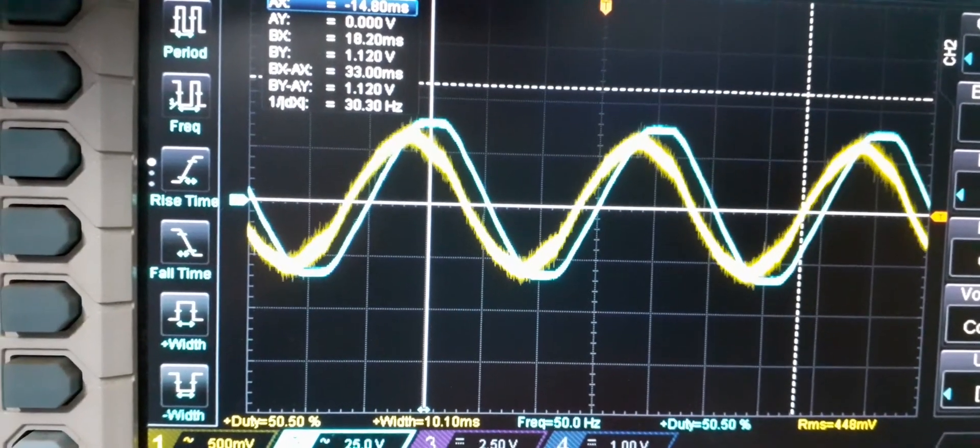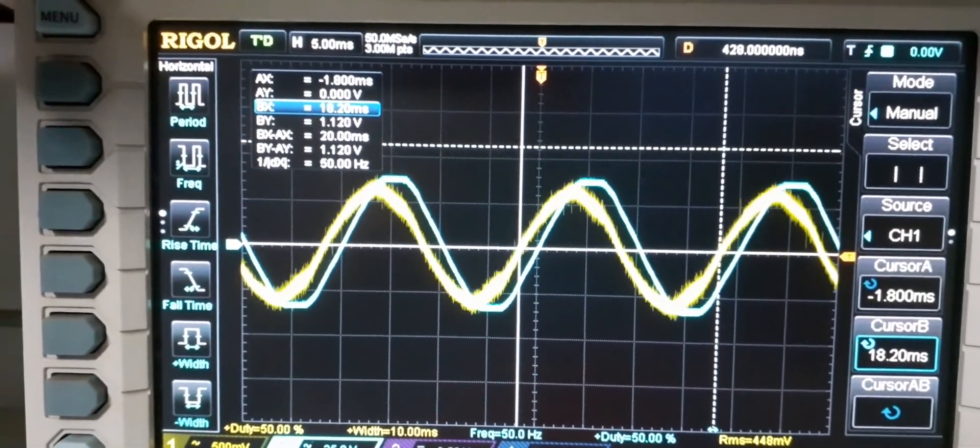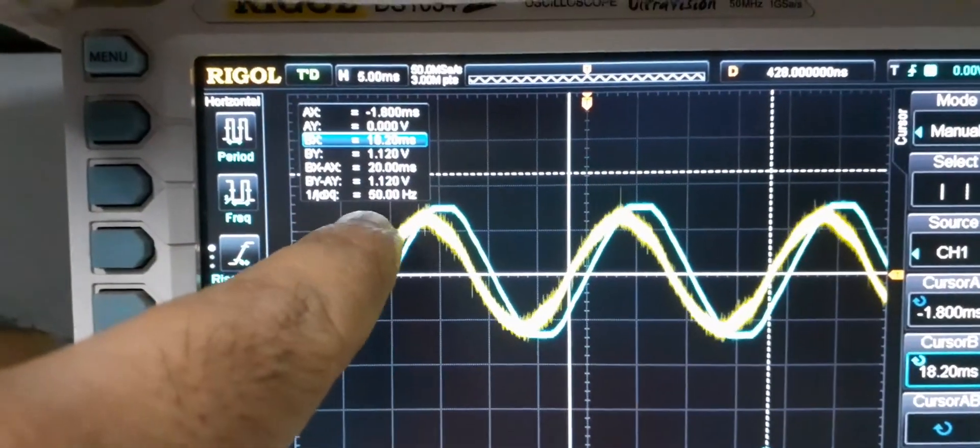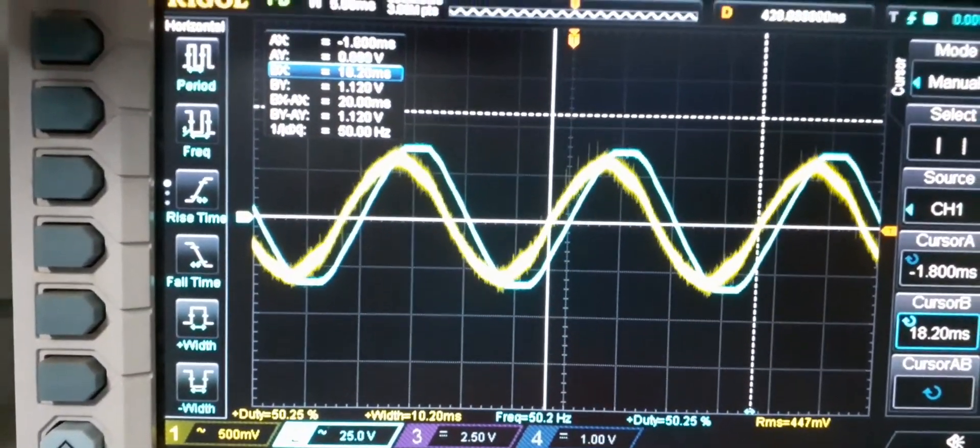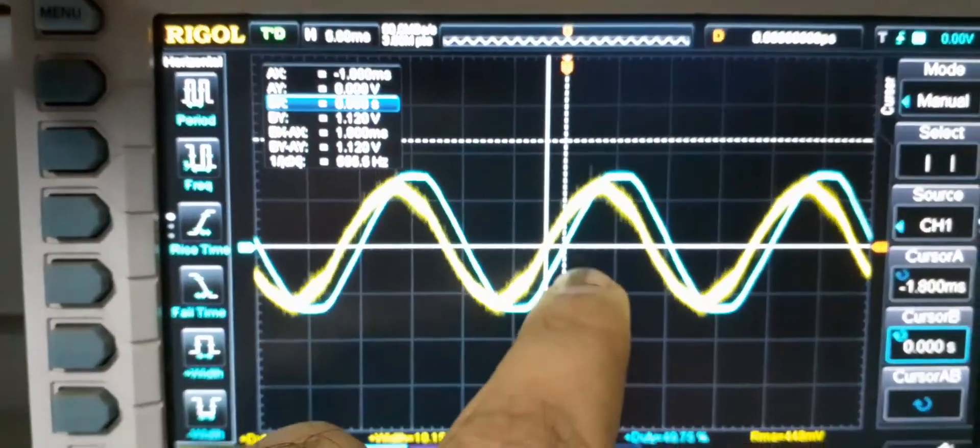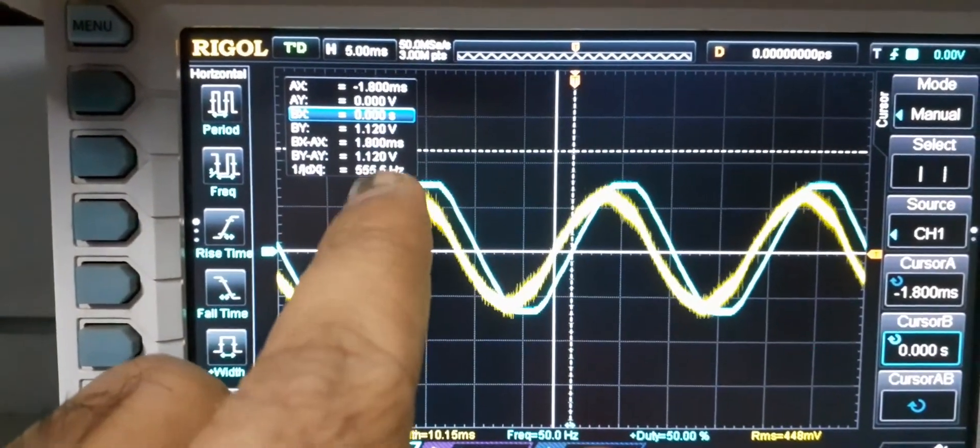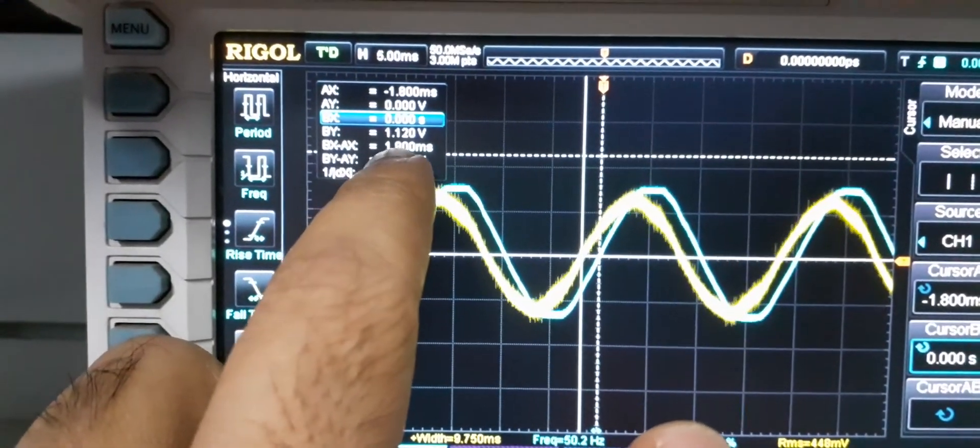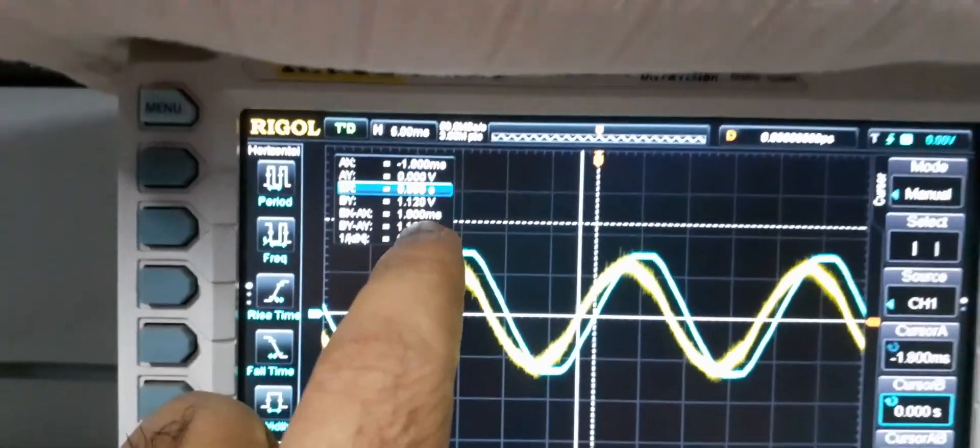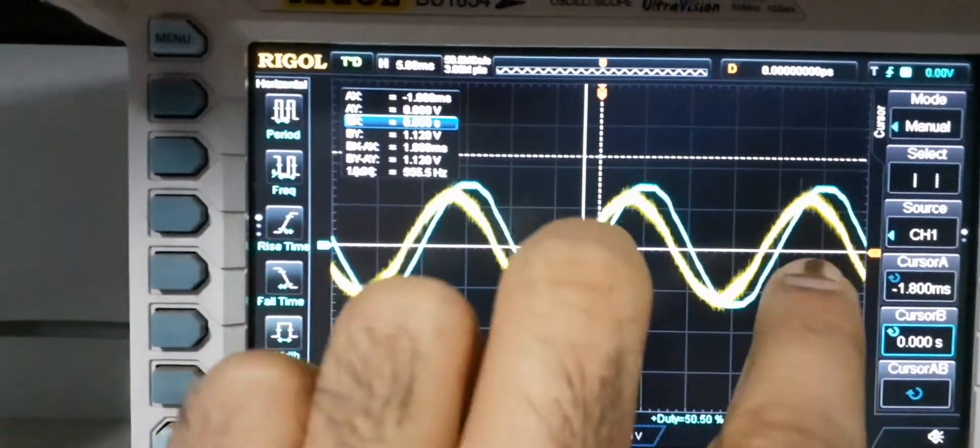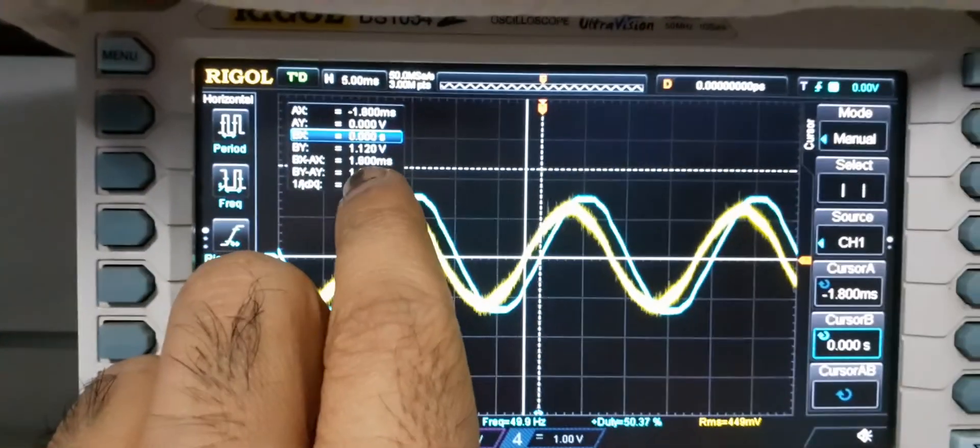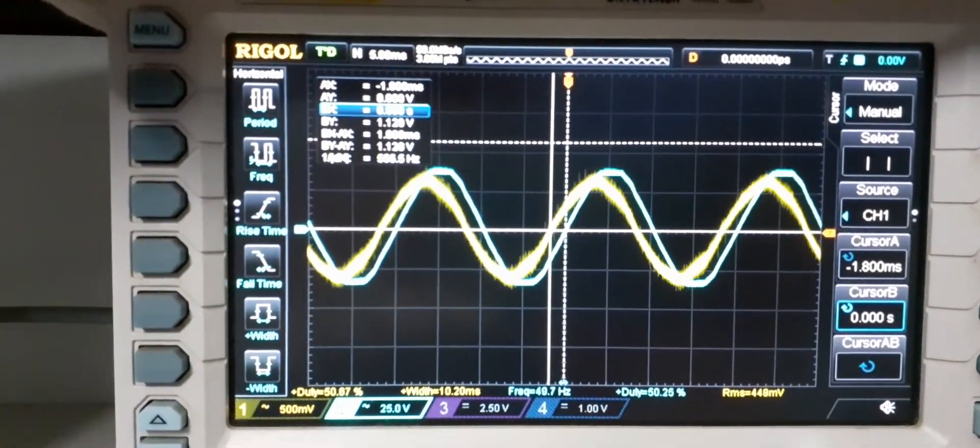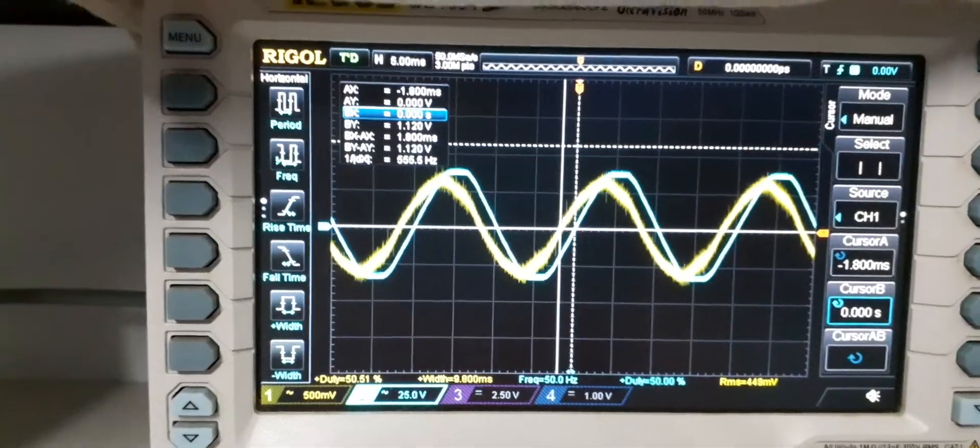How much is it leading? Presently the frequency is 50 Hertz, which is the mains frequency in India. The phase offset is, I have moved the cursor now between these two waveforms, and you can see the phase offset in terms of time is 1.8 milliseconds. 1.8 milliseconds out of the entire 20 milliseconds for 50 Hertz, if we multiply that by 360 degrees, gives us about 32 degrees. So the phase shift is about 32 degrees.